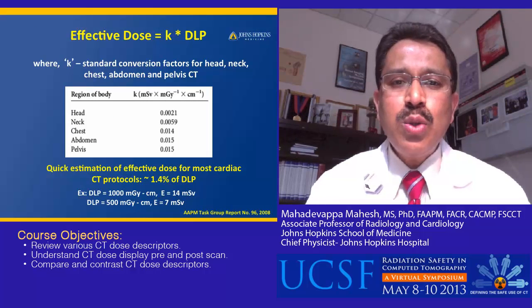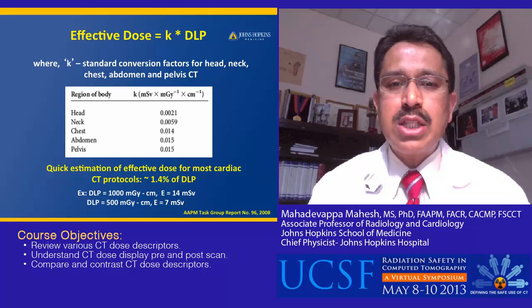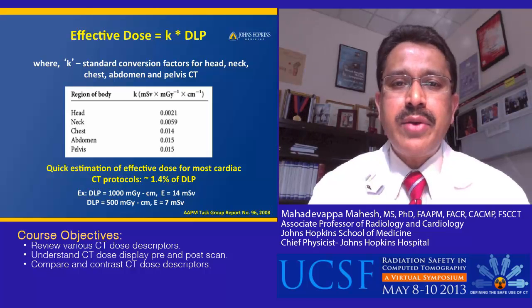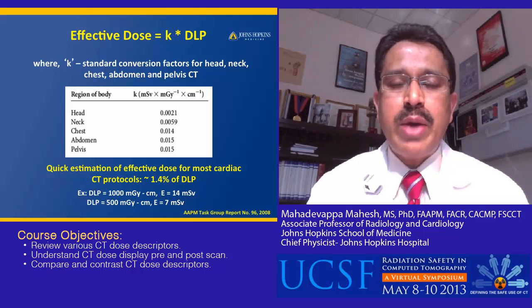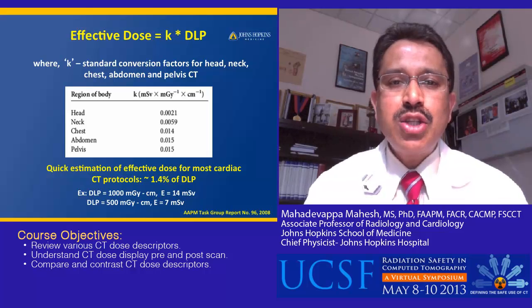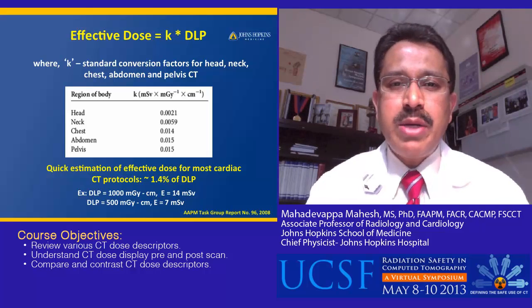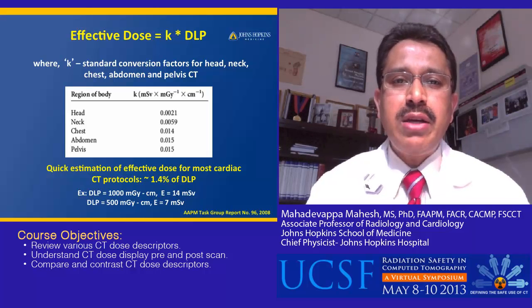There are also well-established conversion factors published by the AAPM Task Group Report 96, which can readily be used with the DLP to arrive at estimated effective dose values. These conversion factors are provided for head, neck, chest, abdomen, and pelvis. For chest, abdomen, and pelvis, a quick estimation is that approximately 1.5% of the DLP provides a rough estimate of the effective dose value.